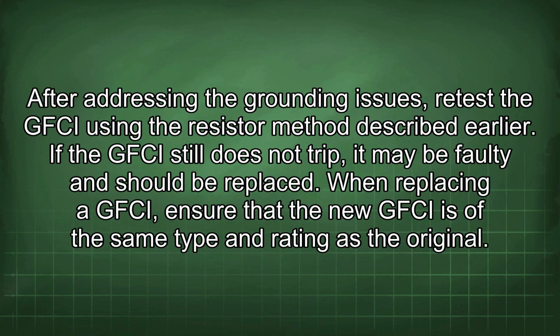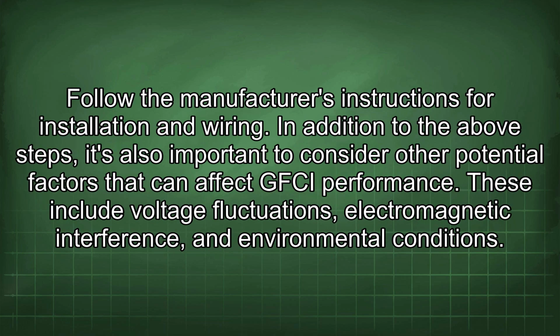After addressing the grounding issues, retest the GFCI using the resistor method described earlier. If the GFCI still does not trip, it may be faulty and should be replaced. When replacing a GFCI, ensure that the new GFCI is of the same type and rating as the original. Follow the manufacturer's instructions for installation and wiring.